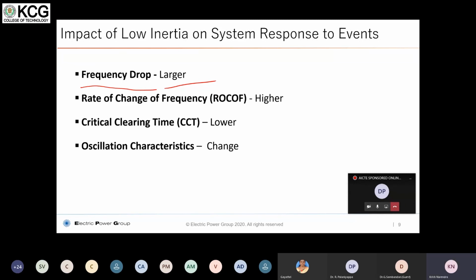Okay, so in case the loads remain the same, but the generation goes off, the frequency has to drop, which is a very large value in case of non-support from the renewables in the system. And likewise, the rate of change of frequency, ROCOF, will go very high because it drops very fast in the system. So that's the second metric.